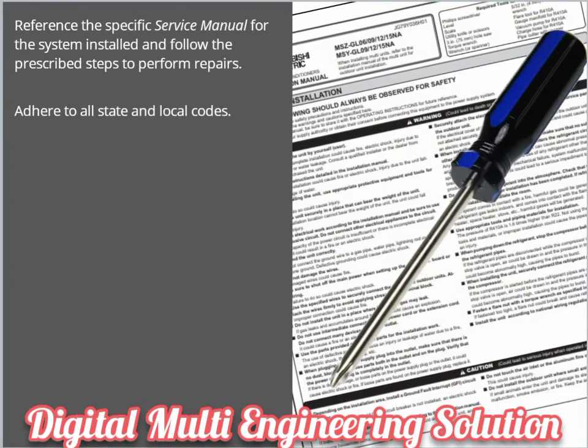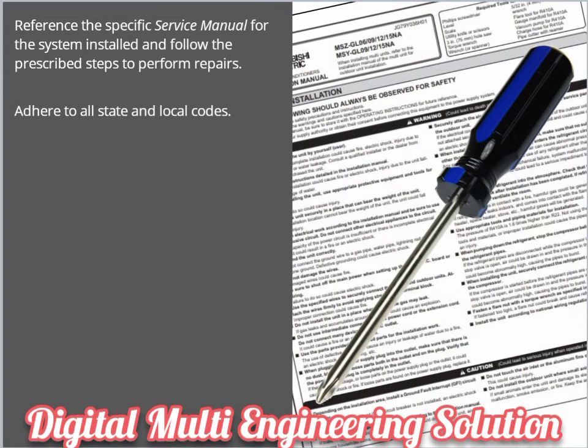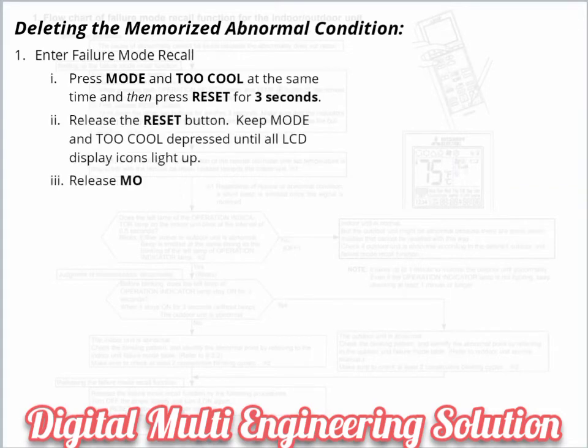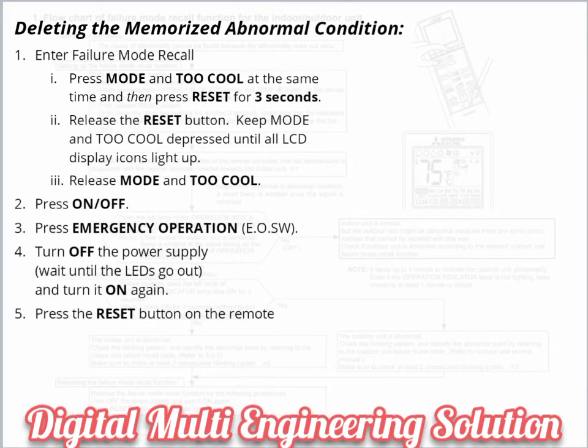Reference the specific service manual for the system and follow the prescribed steps for repair. Be sure to adhere to all state and local codes. Once repairs are completed, the memorized failure code will need to be deleted. To do this, enter failure mode once again. Point the handheld wireless remote controller at the unit and press the On/Off button.